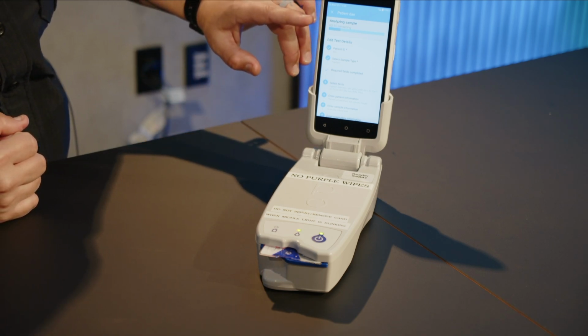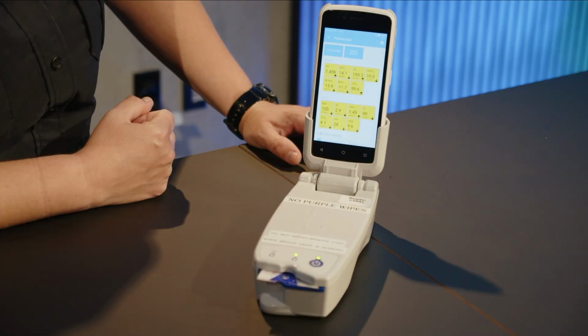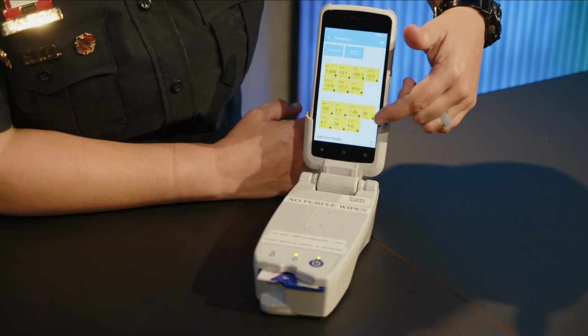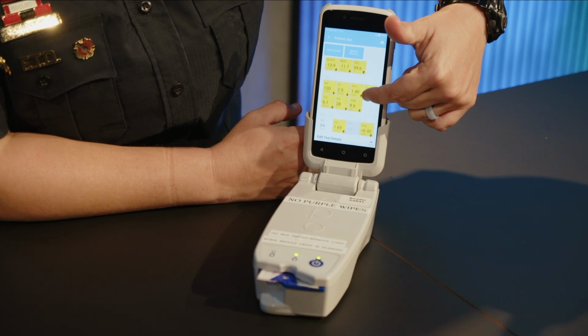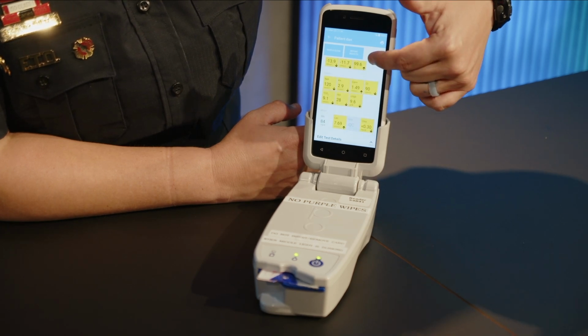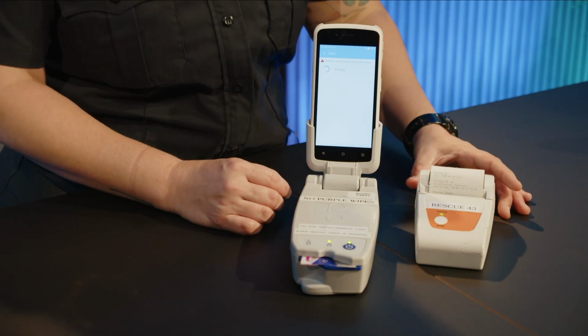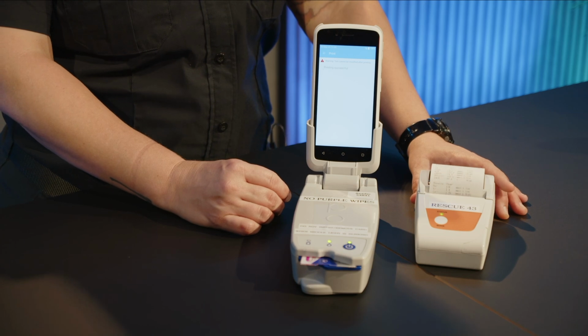Once the test is complete, the results will appear on the host. If all values are within normal range, they'll display in white. If something's out of range, it'll show up in yellow, and if a value is critical, it will show up in red. Go ahead and print the results right from the host, as we'll need that in a later step. If you forget, you can always go back and print them later. The device saves up to 500 test results.